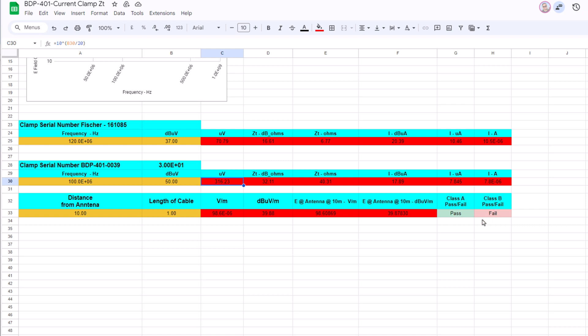Also it compares it to the EMC standards radiated emissions table and it gives you a pass and a fail. And you can see now that it is failing the class B but it's passing the class A, and it does all of these equations automatically.